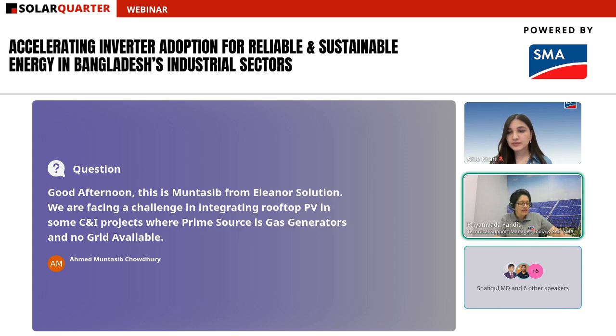But there are gas generators, and basically we need to consider two or three things when working with a generator in a PV system: what is the minimum load requirement for these generators, since we want to avoid any reverse power going to the generator. Also, we want to make sure there is enough reserve, so that if the PV suddenly goes down, these generators can come up fast enough to compensate for the lost PV power.